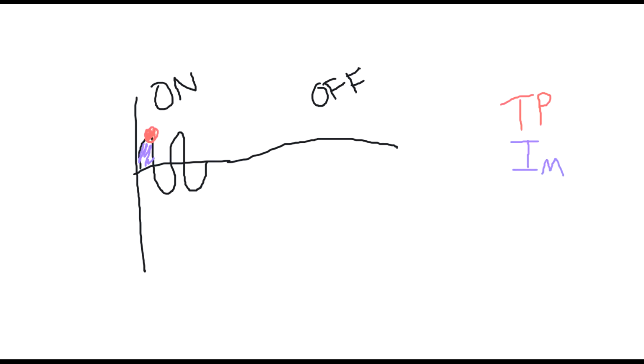And then we have our pulse average. That's just the on time, so it's the average intensity just for the on time. So pulse average. And then we calculate the on time with the off time, and that becomes our temporal average. So temporal average.